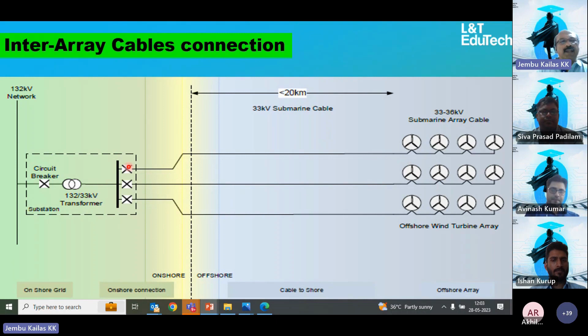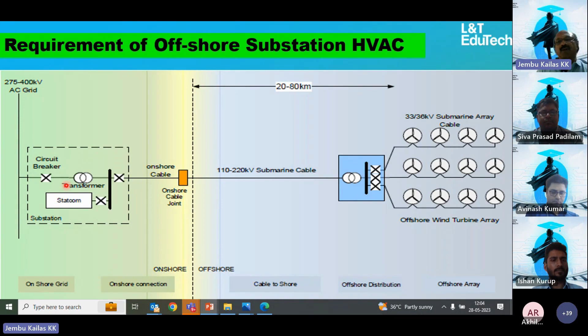If it goes beyond 80 kilometers, we cannot do this, we should have a substation offshore instead, collecting voltages around 33 kV, then stepping up with a transformer to 220 kV before joining the onshore cable and connecting to the substation. This applies within the 20 to 80 kilometer range.